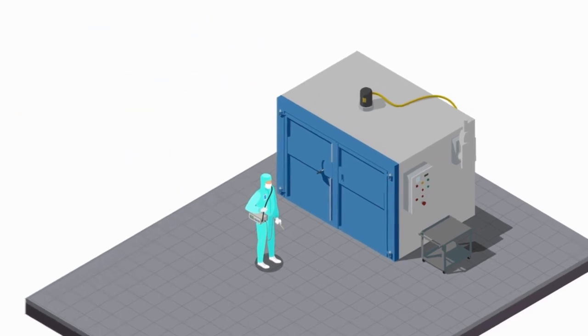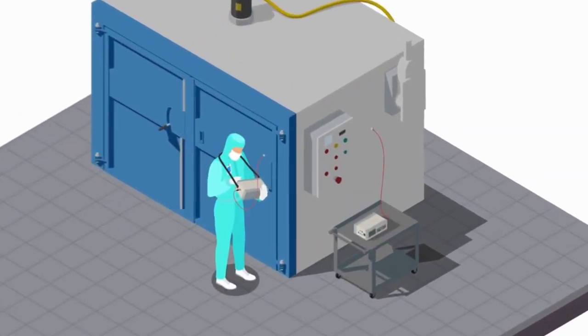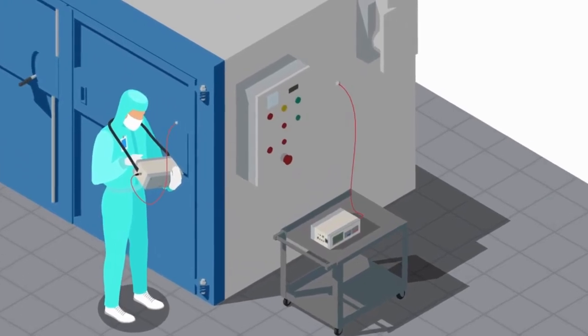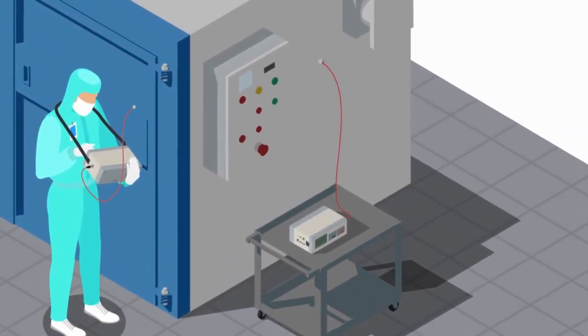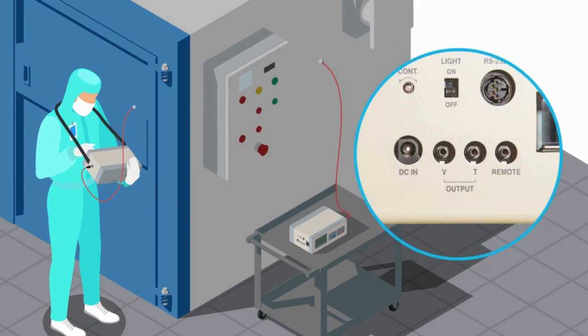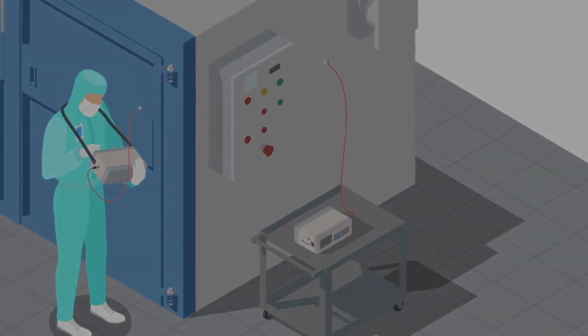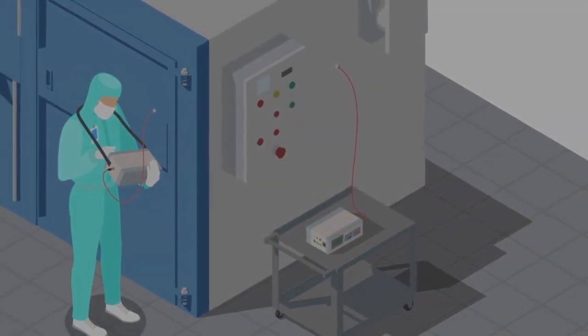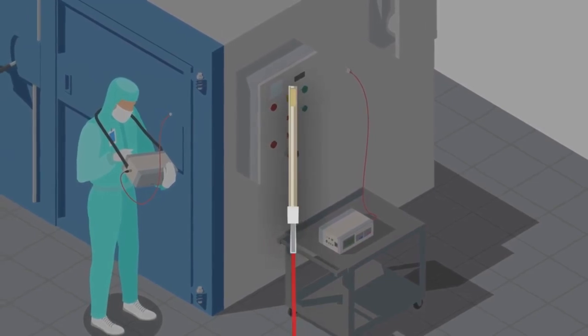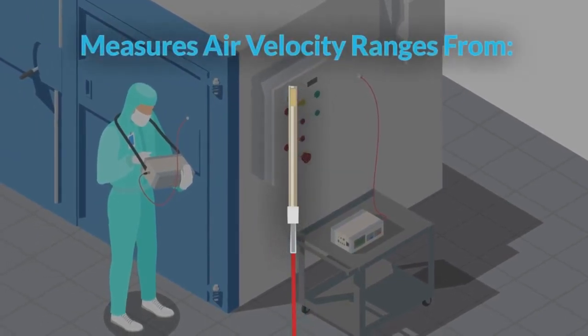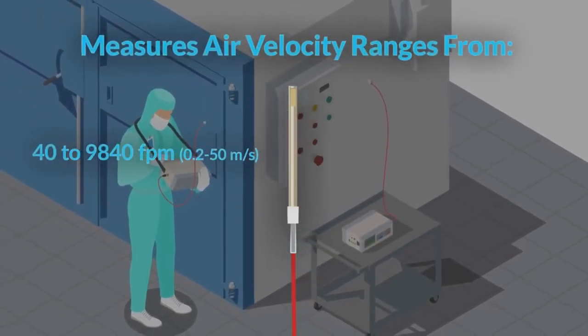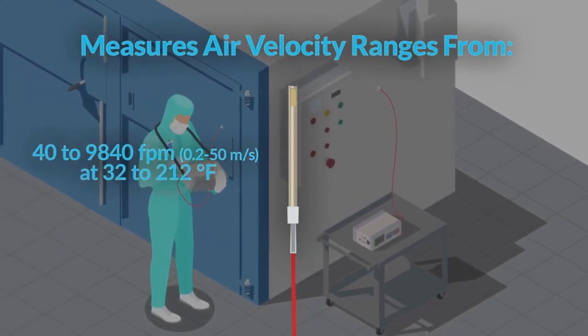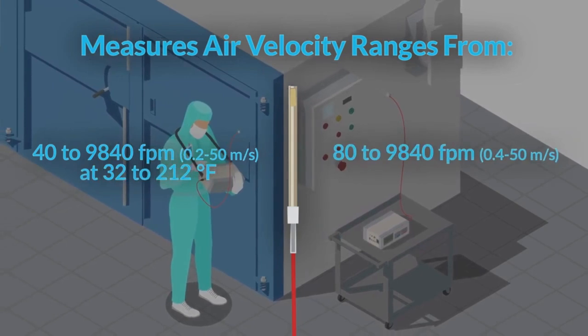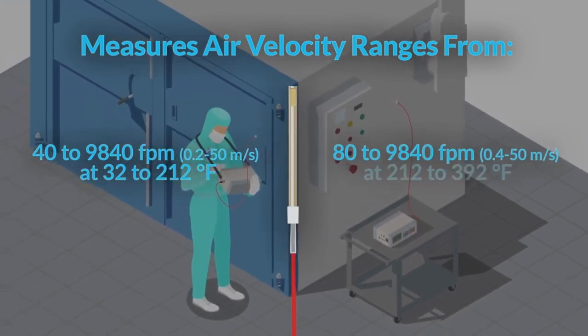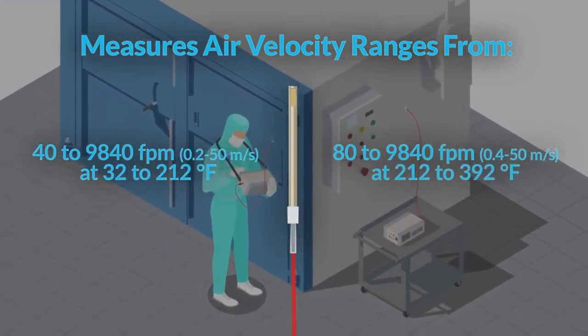If you need to measure multiple points around the oven simultaneously, you'll need multiple units. But thankfully, you won't have to worry about compiling data from each device yourself. Analog output is available for connecting to a data logger or process control device for automation purposes. If the device you're testing operates at temperatures ranging from 32 to 392 degrees Fahrenheit, you'll want to use probe model 0203. It can measure air velocity ranges from 40 to 9,840 feet per minute at 32 to 212 degrees Fahrenheit, and 80 to 9,840 feet per minute at 212 to 392 degrees Fahrenheit.